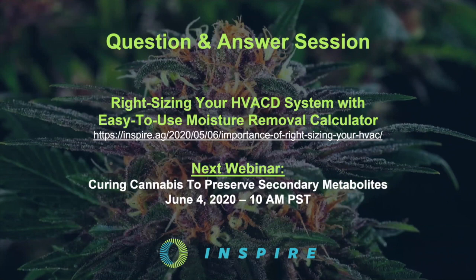Jesse, do you have anything to add? No, I think that was really good. When it comes to recirculating, it's better to make a really good stab at trying to do it right than to think about the minor implications that you might have for that recirculated air. We know that stale and stagnant air is going to be a health issue for people and plants. And just like you mentioned, as far as an integrated system, it's probably looking more like some sort of capture filter, like a MERV 13, followed by some sort of secondary treatment, whether that's UV or photocatalytic oxidation, in order to make that recirculation path make sense for a long period of time.